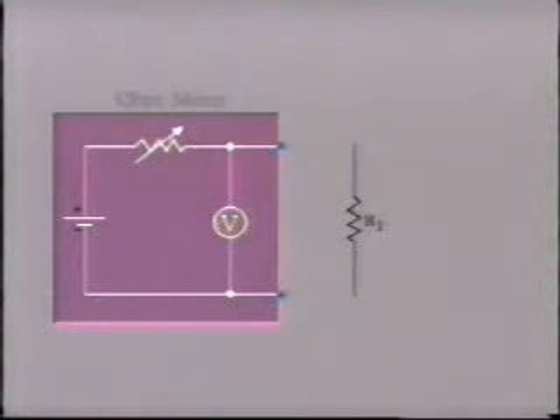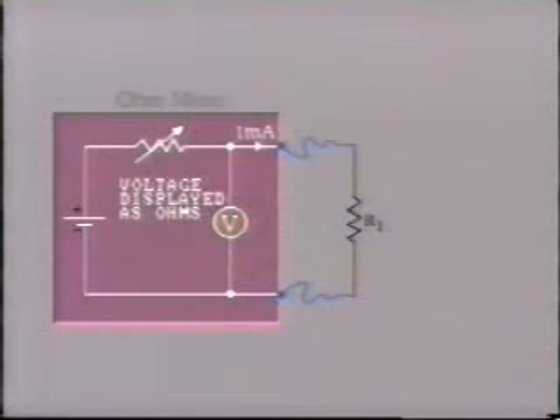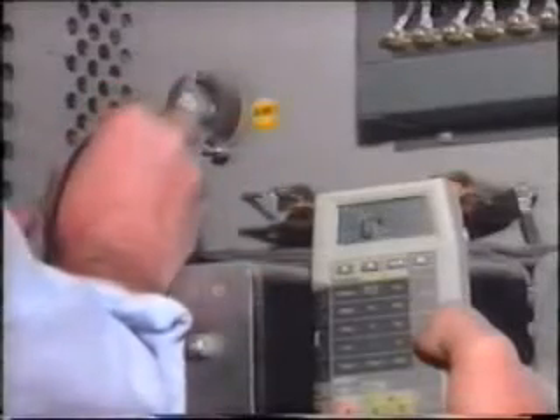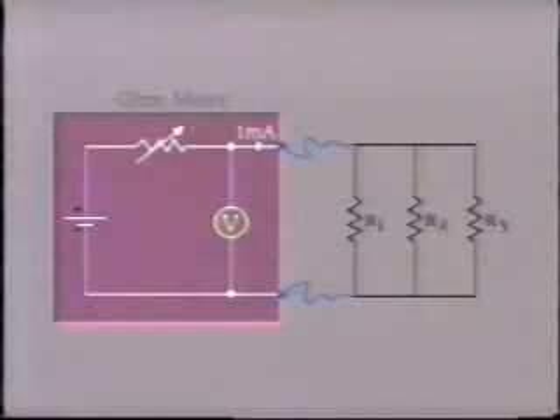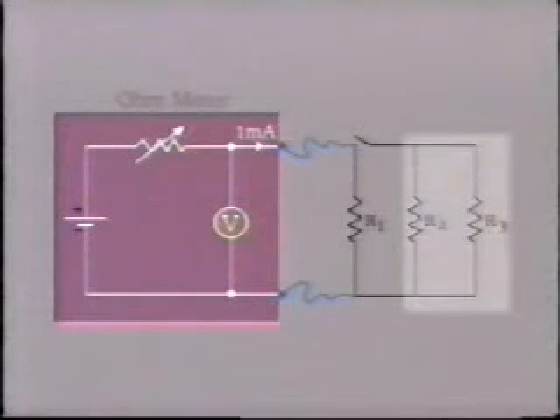All right, let's move on now to look at measurement of resistance. Most ohm meters work on the principle of injecting a small DC current, say 1 milliamp, into the circuit under test. By measuring the voltage drop across the circuit, the resistance can be calculated and displayed. It is important that the circuit be de-energized before attempting to measure resistance. Also, when measuring the value of a resistor in a circuit, you should always lift one lead so as to avoid the possibility of parallel current paths, which will, of course, result in a lower resistance value.